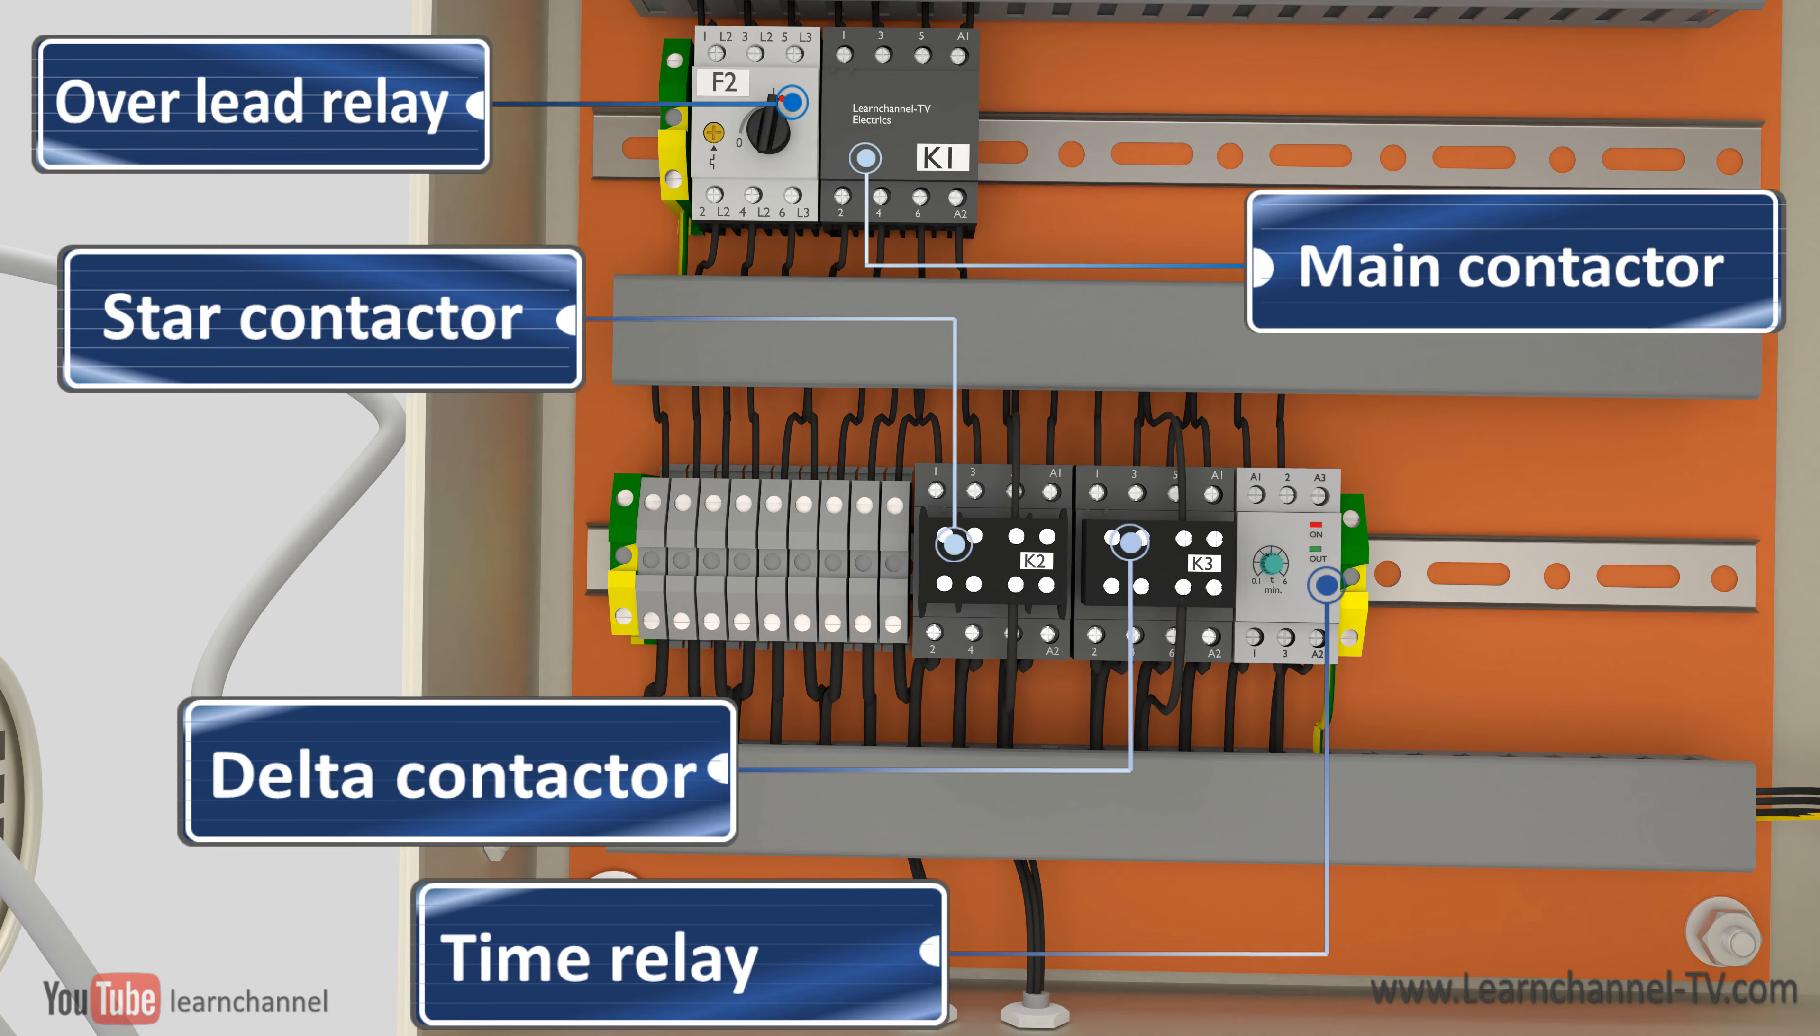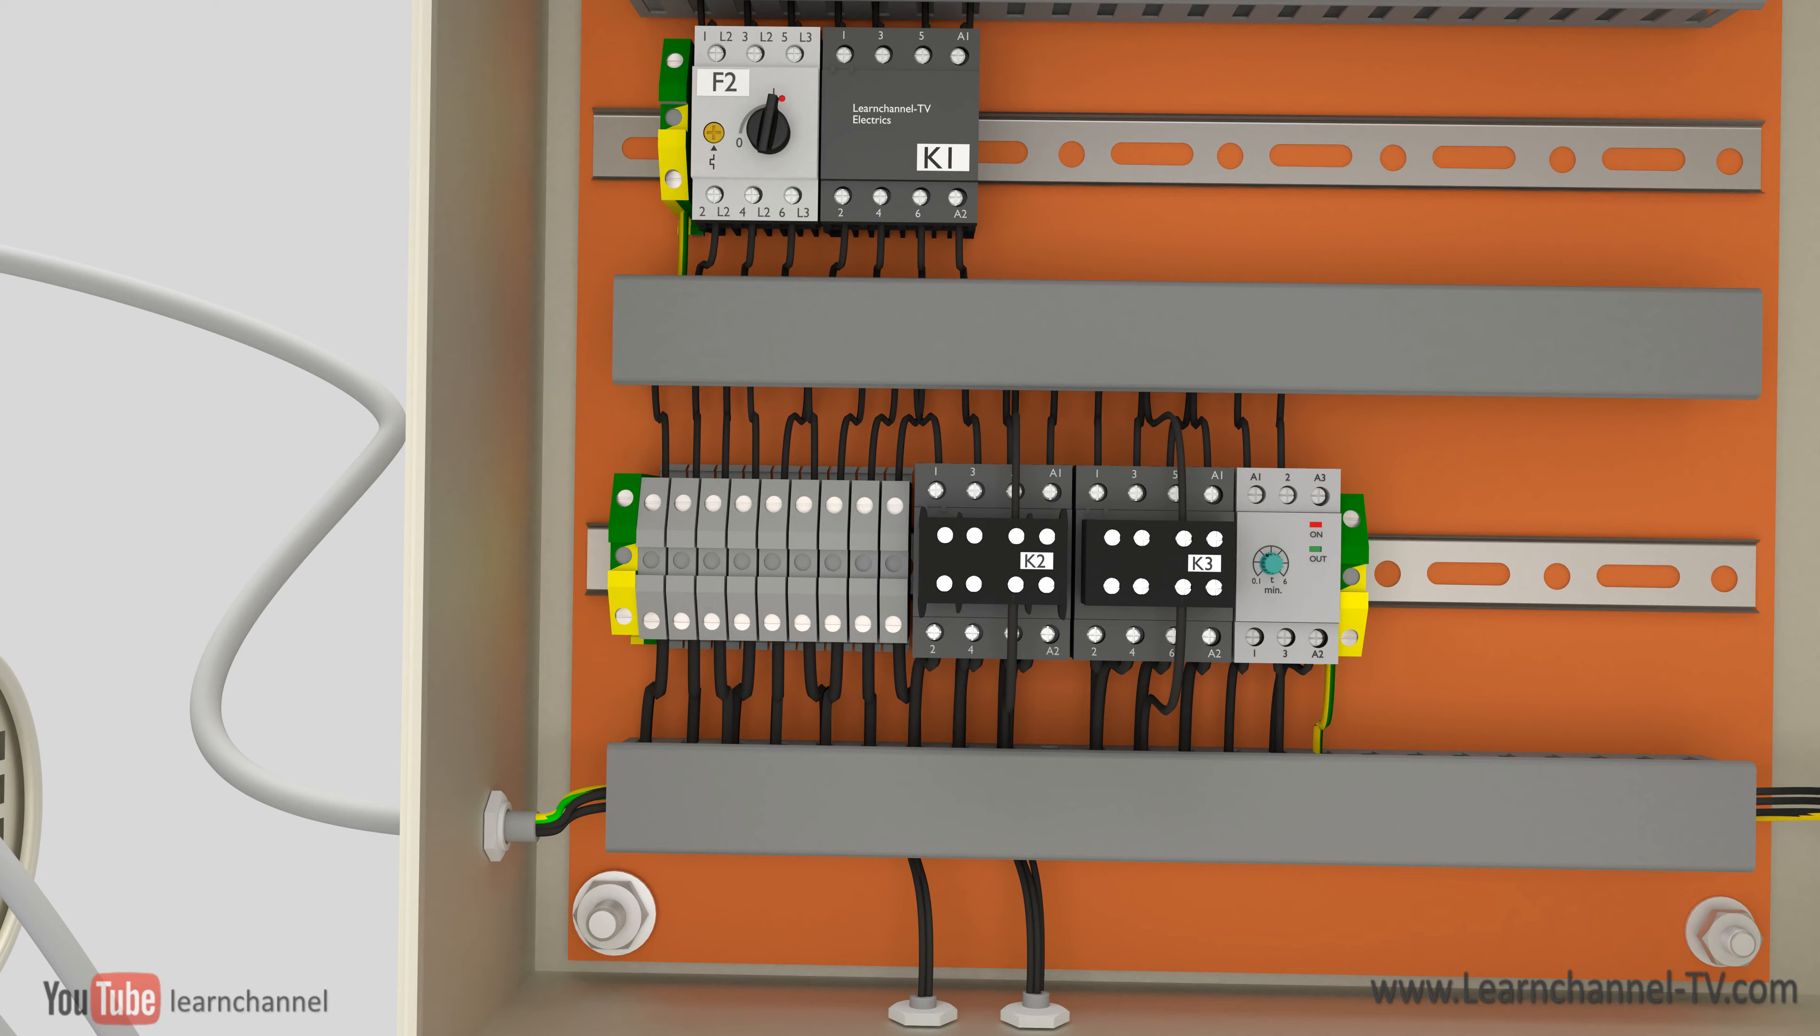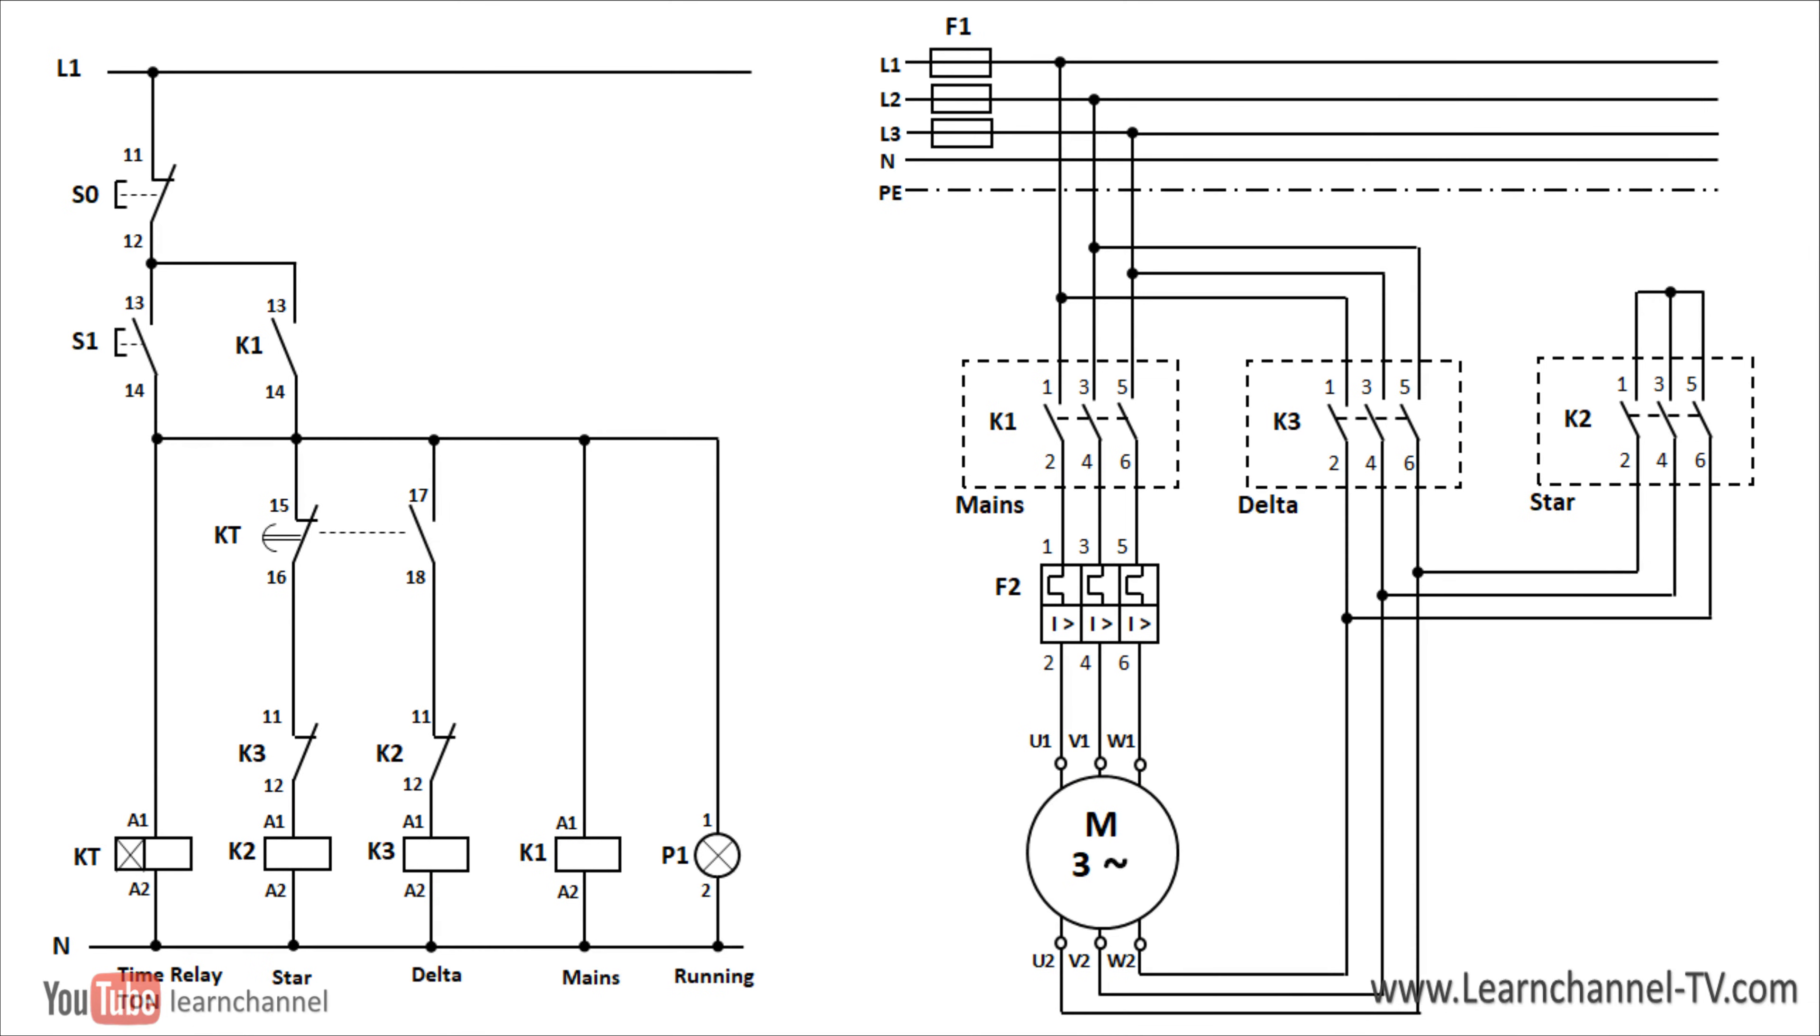Here you see the necessary components. For a better understanding, let's discuss the electric circuit of our control. As soon as the start button is pressed, the main and star contactors are energized. The three-phase motor now starts in star mode. The main contactor holds itself and bypasses the start button.